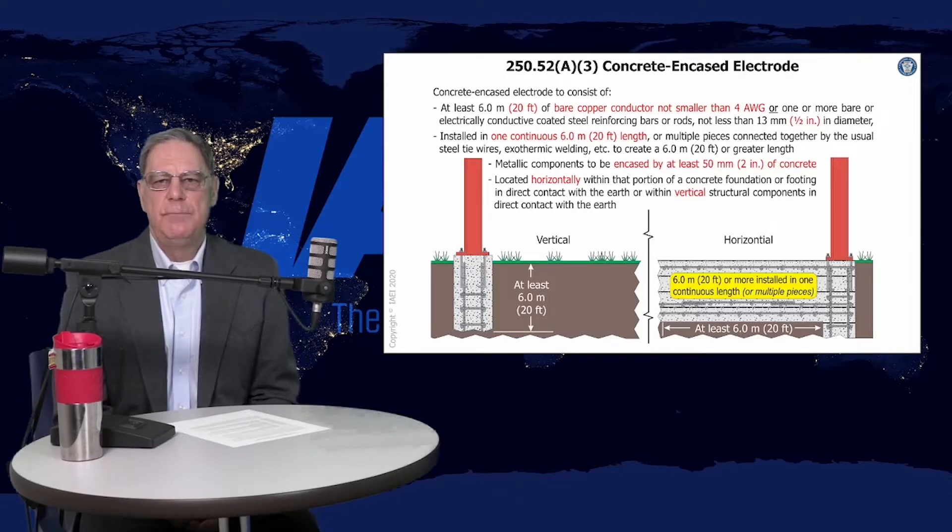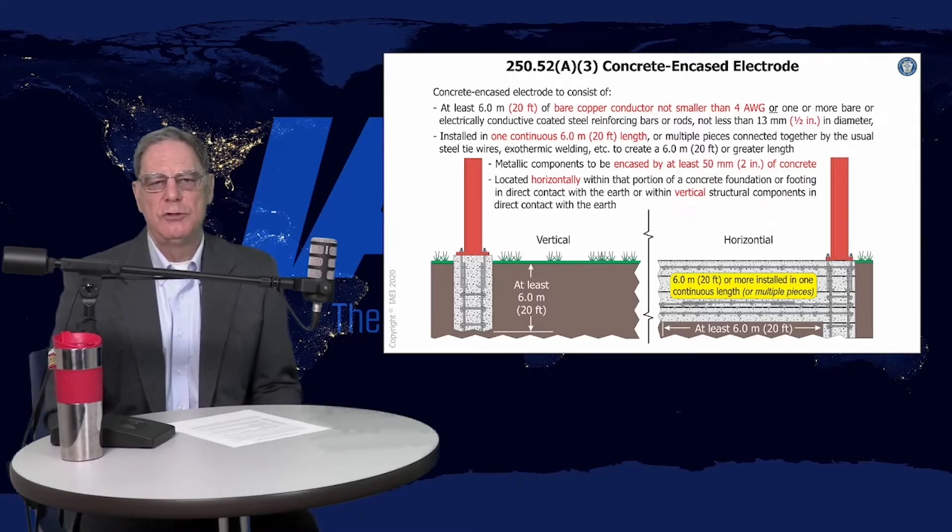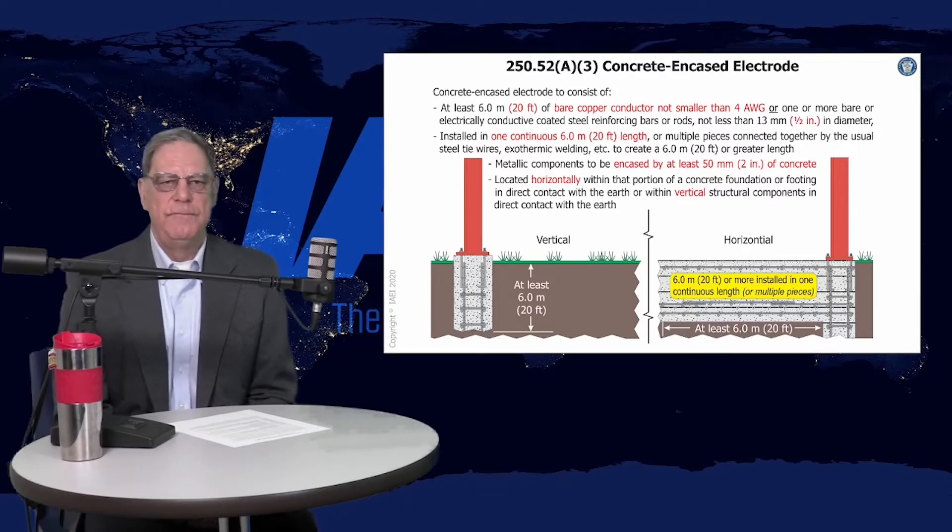At least 20 feet of bare copper conductor, not smaller than 4 AWG, or one or more bare or electrically conductive steel reinforcing bars or rods, not less than a half inch diameter. The reinforcing bar can be in one continuous length or in multiple lengths that make up that 20-foot length with the usual tie wires.